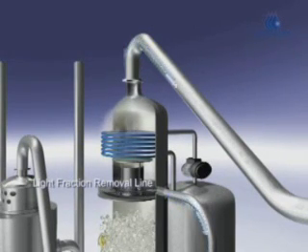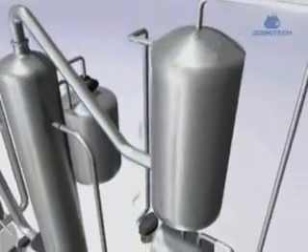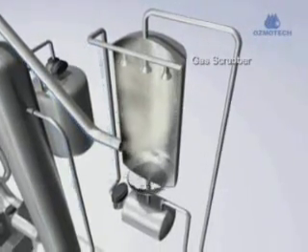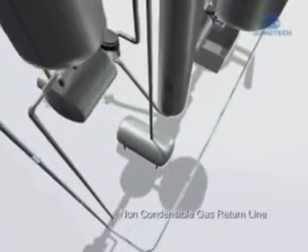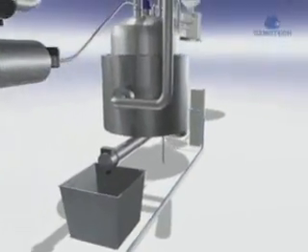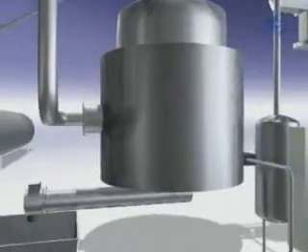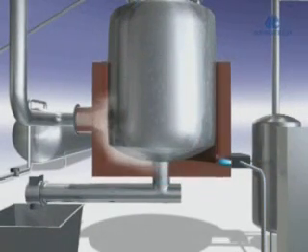The non-condensable gases pass out of the distillation column, then to the gas scrubber, where sulfurs and other impurities are scrubbed by an alkaline wash. The gases are then returned to the main furnace as an additional heat source. This adds significant efficiency to the system's operation, and because of its closed-loop configuration, thermofuel emits extremely low levels of emission to atmosphere. From the main furnace, exhaust gases are vented and used to heat the catalytic converter.